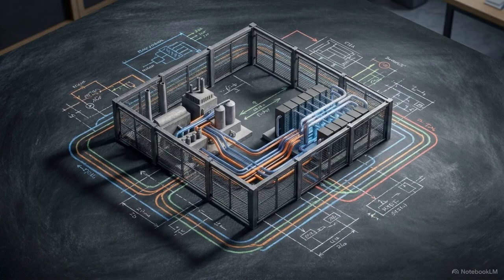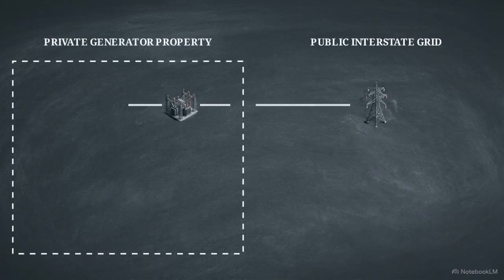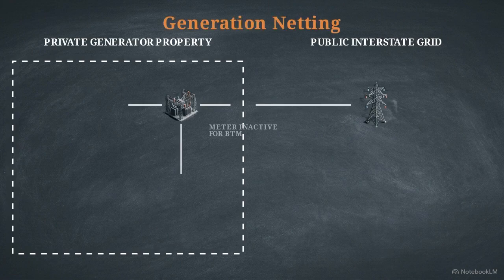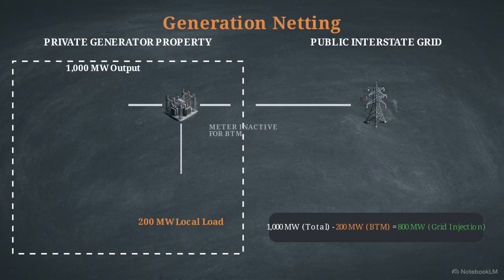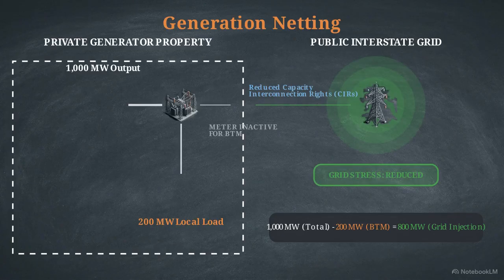A behind-the-meter physical integration bypasses this hazard. The data center hooks directly into the generator's side of the substation, consuming the power locally on private property before it ever reaches the interstate transmission grid. This model illustrates generation netting. If a 1,000 megawatt power plant routes 200 megawatts directly to an adjacent server facility, it drops its transmission output to 800 megawatts. By injecting less power into the public grid, the generator officially reduces its capacity interconnection rights.